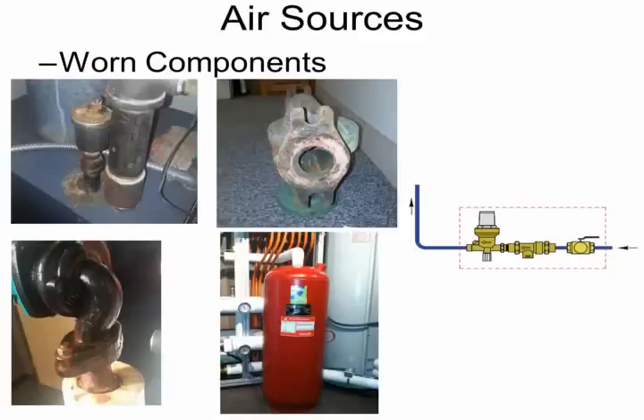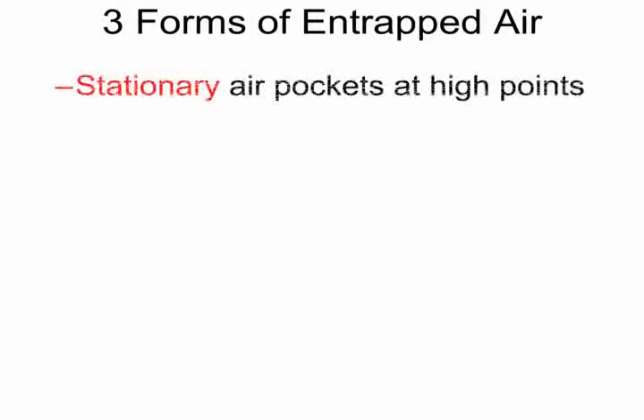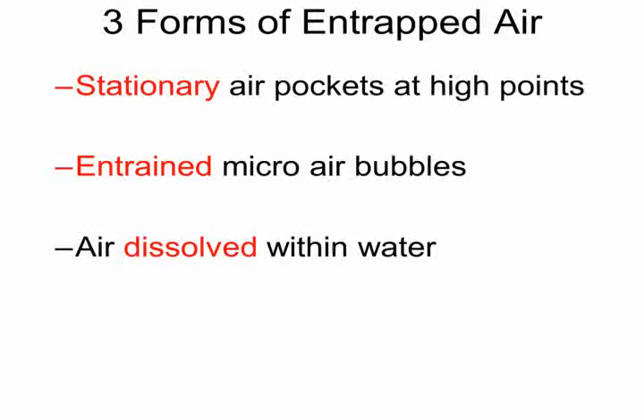The acceptance volume is going to become reduced more and more, and introducing more and more water into the system as the makeup tries to keep the pressure on. And that's not so readily identifiable by looking at it versus some other components. So even aging expansion tanks can cause air to get into a system.